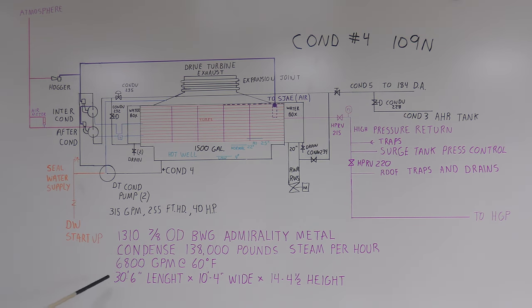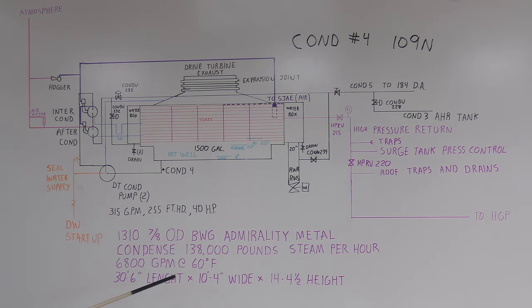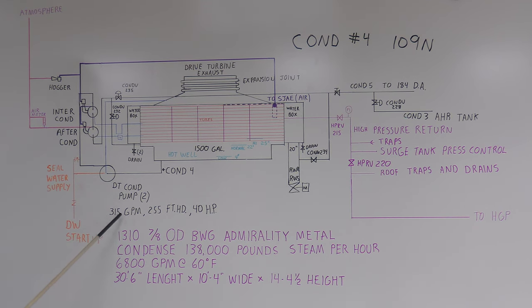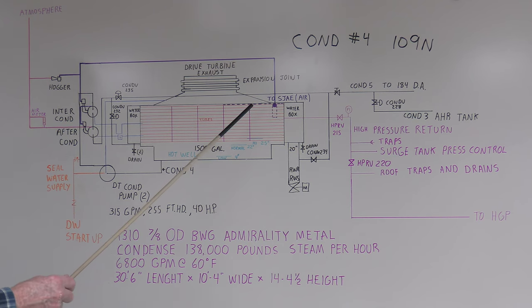Now the condenser is 30 foot 6 inches long, 10 foot 4 inches wide, and 14 foot 4.5 inches high. The dump condensate pump put out about 315 gallons a minute at 255 foot head with a 40 horsepower motor. It had drains on each end for draining, and then there's manways you could get into to check for tube leaks.